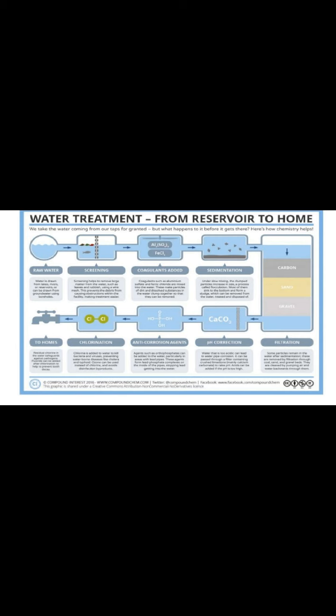Coagulants make the particles of dirt and dissolved substances in the water clump together so that they can be removed easily. Fine solid matter suspended in water — colloidal matter — does not settle down at the bottom of the sedimentation tank on its own. Coagulants are added before sedimentation to clump the colloidal solid matters. The coagulants destabilize the particles, then water is transferred into the sedimentation tank.